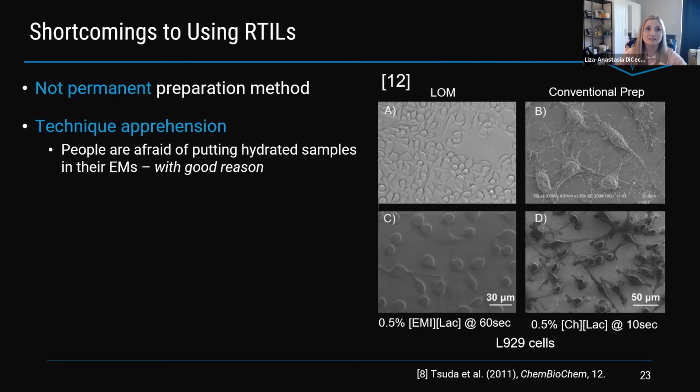We always do a safety vacuum check of our samples beforehand, where we just leave them in vacuum so we know excess solution that would evaporate in the system evaporates out of the system. When we're doing it on a microscope with low and high vacuum possibilities, we always do low first, and we check the surface to make sure there's no excess liquid pooled on the surface that would cause us trouble in high vacuum. And when I'm on our Magellan, we have a quick loader system.